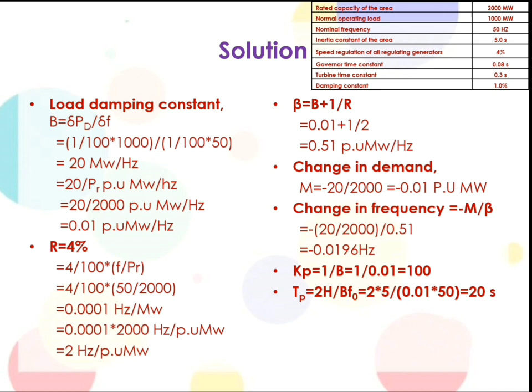Here we determine the Kp, that is the gain constant of the generator, which is equal to 1 by B, which is equal to 1 divided by 0.01, is equal to 100. Similarly, Tp is equal to 2H divided by B f0, which is 2 into H value, given as 5, divided by B value, which we have already found as 0.01, and f0 is the base frequency or the nominal frequency, 50 Hertz, which is equal to 20 seconds. So now we have determined all the parameters that are required for the model.